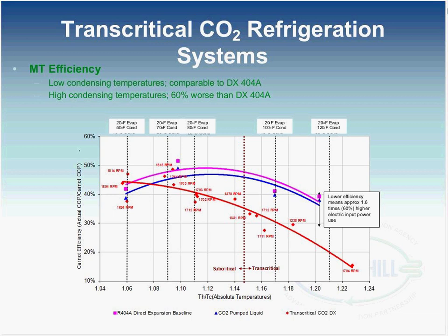Not to get too caught up in the axes, but the ratios have been done to provide a non-dimensional number in order to do an adequate comparison, so we can get relative performance of these systems to each other without having to look at specific conditions. So looking at this slide, at the more traditional temperatures where you're condensing above 100 degrees, you'll see that the red line is significantly below the purple and the blue lines. It actually starts happening around the 60 to 70 degree mark, where you see the performance start dropping considerably. So this is where the system starts operating in a transcritical mode.